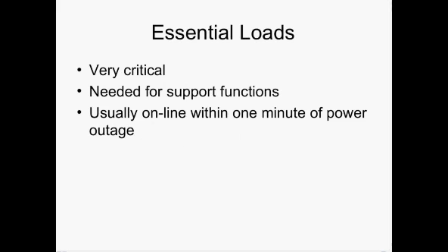Life safety loads are applied to the emergency generator first. Typically, the emergency diesel generator set restores power to the life safety loads in 10 seconds or less from the time the utility power outage is encountered. The essential loads are put on a few seconds later. The third item is the other loads, and these are applied last. This allows the facility flexibility to apply multiple transfer switches to the emergency diesel engine generator set.